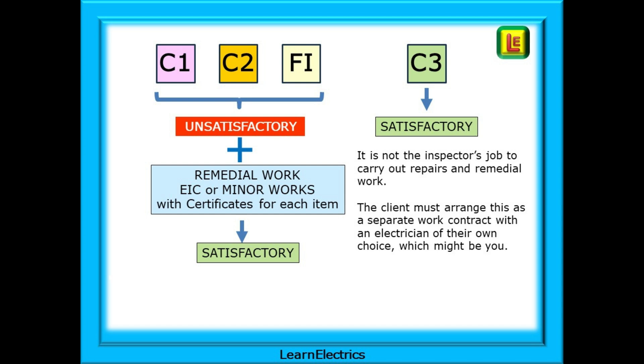There is no need for you to carry out another inspection. Your obligations were complete when you issued the original EICR and your invoice. Having said that, it often happens that you are asked to complete the remedial work. The C3 code is used where your observations show minor deviations from the current regulations, or items that, although not dangerous, would benefit from some attention. C3s only on an EICR will leave the report as satisfactory.